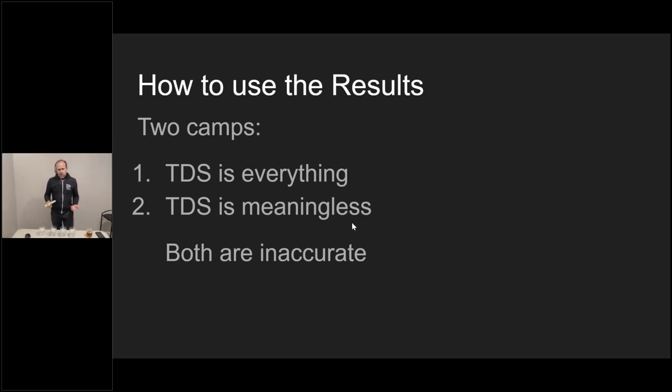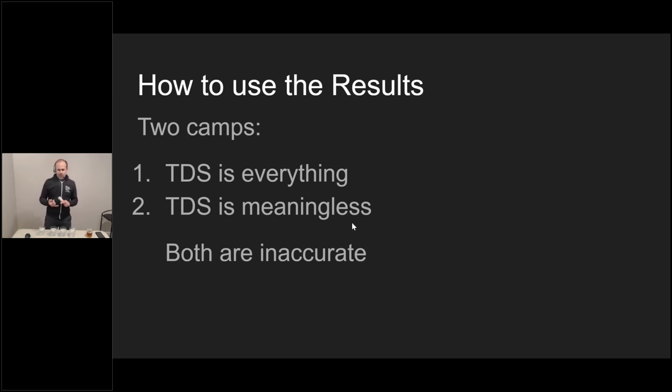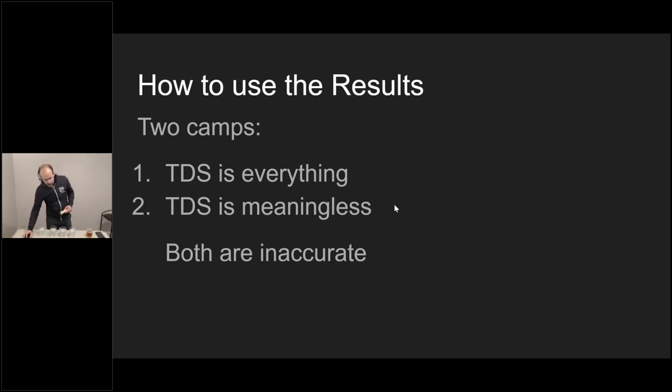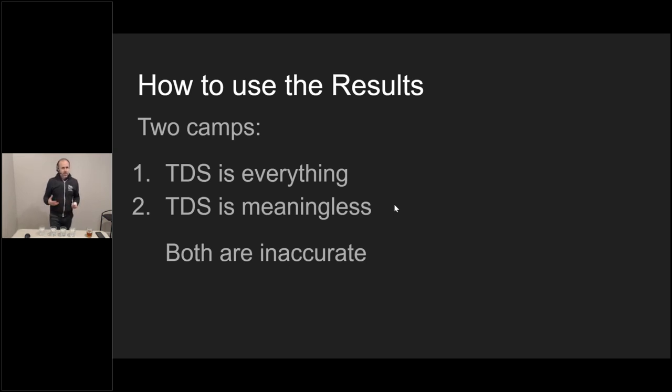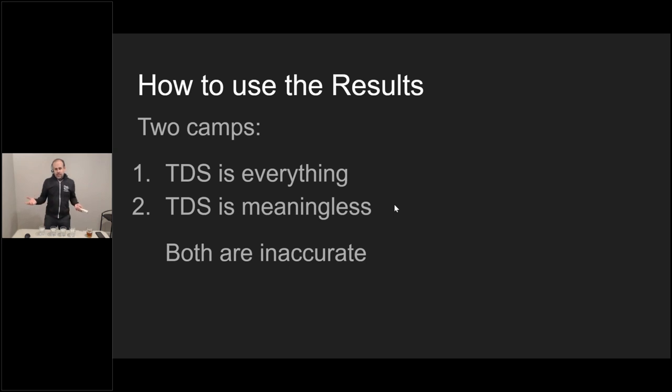So how do we interpret these results? I gave you some indication about how you can use a TDS meter, verifying a permeate stream off of an RO system to make sure the RO system is functioning properly. You can also use it as a sum of the concentration of analytes. If you were to take and measure individually, either with test strips or drop count titration or a spectrophotometer, your total hardness, your alkalinity, your iron and your chloride, and you were to sum all those up, just add all the parts per million, it's going to be somewhere approximately what you're going to see on your TDS meter if everything's working properly.